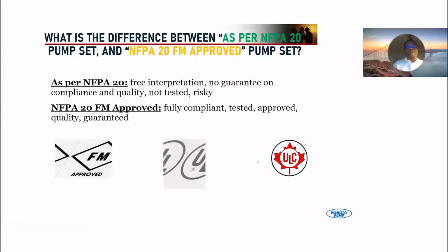So the last thing that I'll talk about a little bit in the preamble is you might get a little bit of discussion surrounding, well, I just want a pump as per NFPA 20, or we like to go NFPA 20 but FM and UL approved. When people talk about NFPA 20 or as per NFPA 20, there's usually a free interpretation. It doesn't guarantee that your pump meets requirements and quality, or that it has gone through the strict process that the independent authority has made sure these pumps, they're stress tested to meet their requirements.